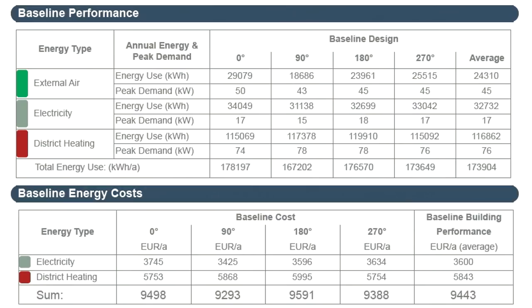The Baseline Performance Chapter's Zero Degrees column displays the original unrotated baseline building's performance data, while the three additional columns contain the performance data of the rotated baseline building versions, and the last column displays the calculated average values. The Baseline Energy Cost Chapter lists the operation costs of each baseline building variation. Note that in this example project, there are two rotated baseline building versions — 90 degrees and 270 degrees — that would cost less to operate than the building with the designed orientation. Unfortunately, site conditions such as adjacent buildings and street positions determined the building orientation, so possibilities for further optimizing thermal block positions and glazed openings are limited.